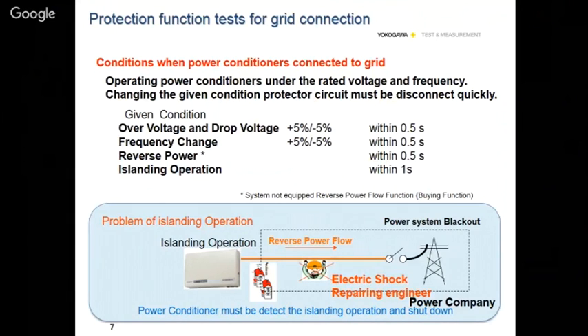On one side I am analyzing the voltage drop and over voltage, whether it is plus or minus 5%. Sometimes the protection circuit trips even when the voltage deviation is less than 3%, which means our set limit is not okay. When reverse current or reverse voltage flows, obviously it should trip. And islanding operation sometimes happens, maybe like an avalanche, and in that case it should trip within 1 second. Here accuracy is not the criterion. The over voltage and drop is plus or minus 5%, the frequency change is plus or minus 5%, and the critical parameter is timing.